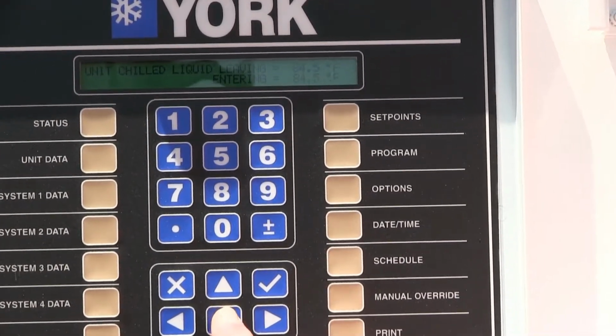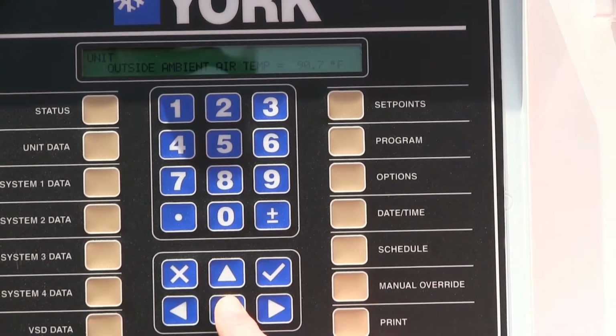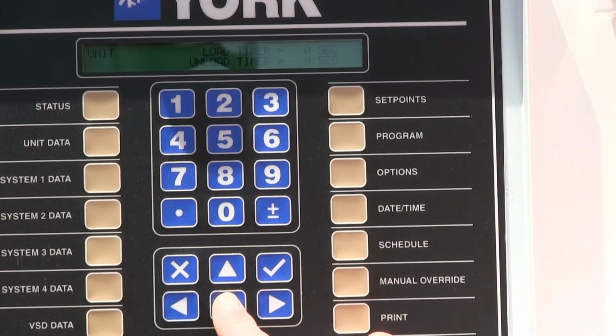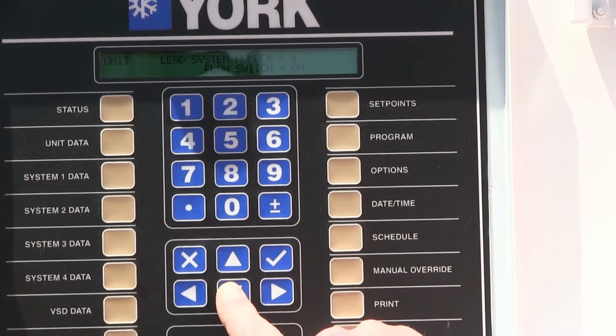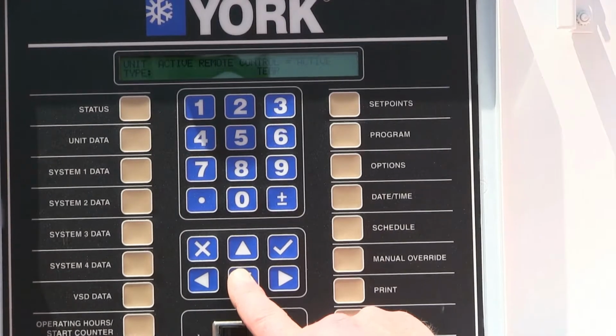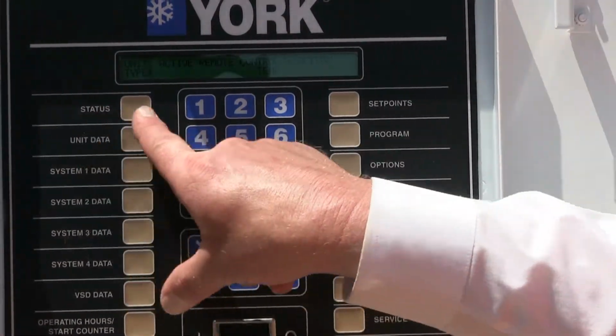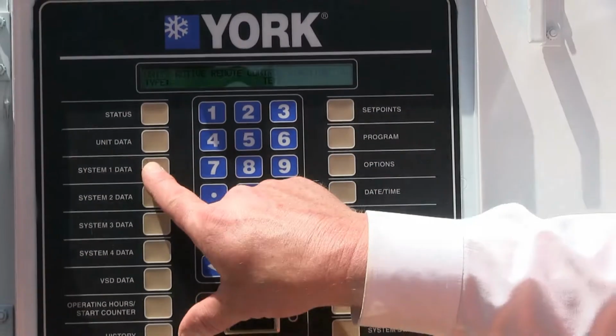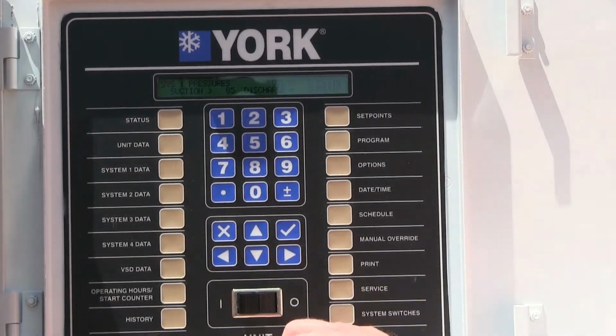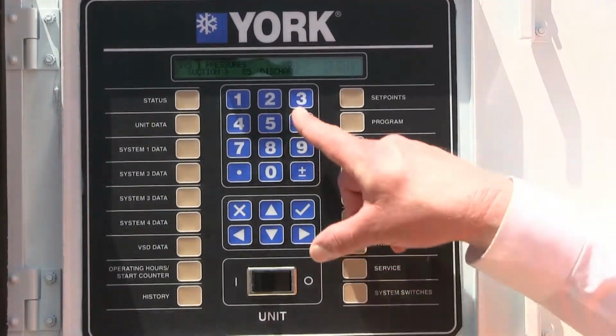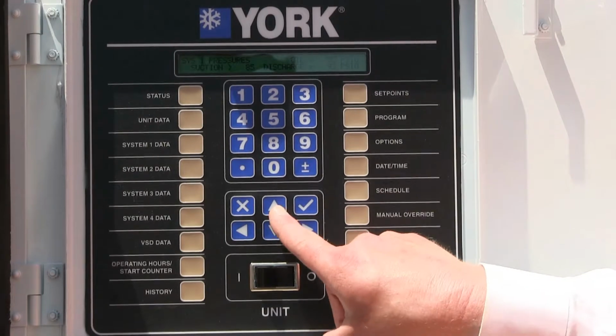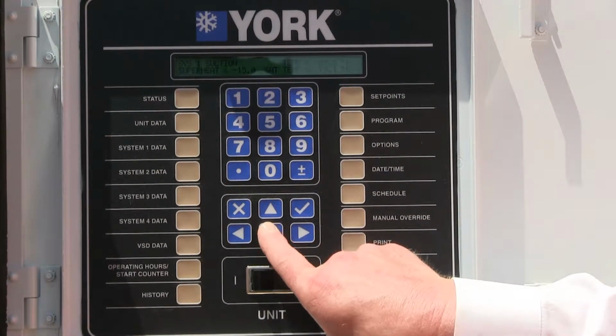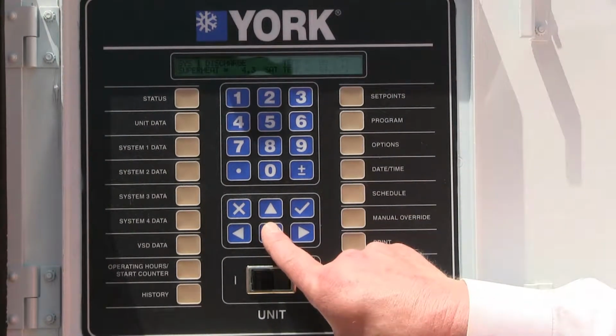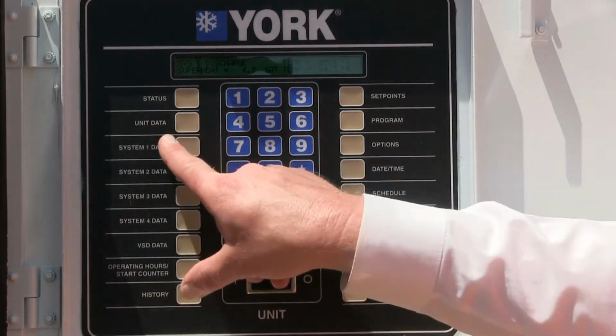Once you're into the unit data menu, you can simply arrow down. That'll tell you the ambient temperature is about 91 degrees out here. That'll tell you your system number, your pump is running. Again, this is just data here, nothing to change. Same thing with system 1. If I go to system 1, that's going to tell you my refrigerant pressures, being suction pressure, discharge pressure, all of my temperatures, superheat, subcooling, all the technical data associated with system 1.